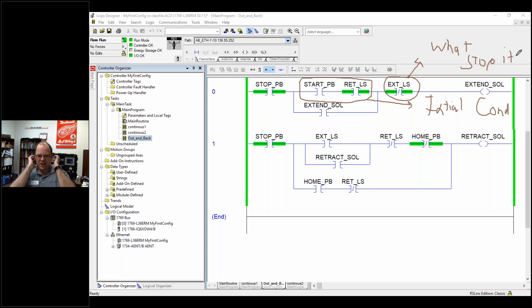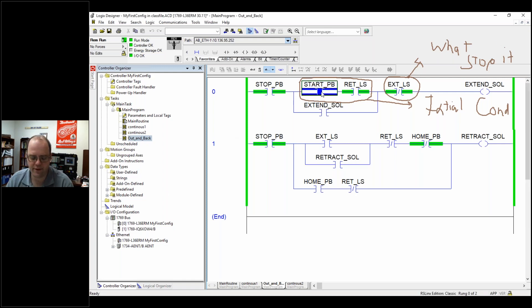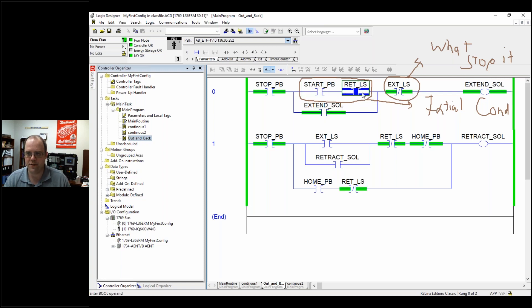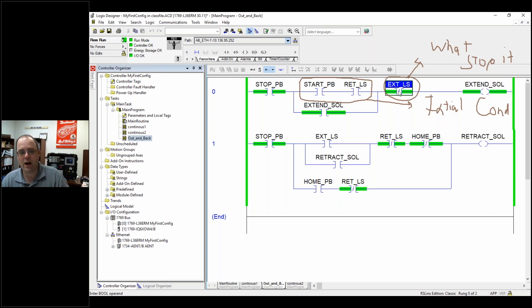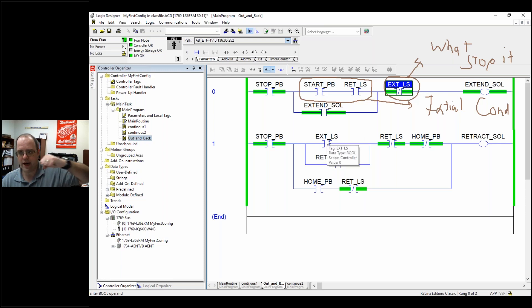This is a format you can use to start getting you to think about it. So now I have my stop button engaged and I'm going to toggle. I hit start and you can see it extends the solenoid. As it comes off, it's going to go off this limit switch, which is still running. So it's extending, extending, extending until it hits the end of travel. Once it hits that extended limit switch, it's going to drop that out and then engage the retraction solenoid.